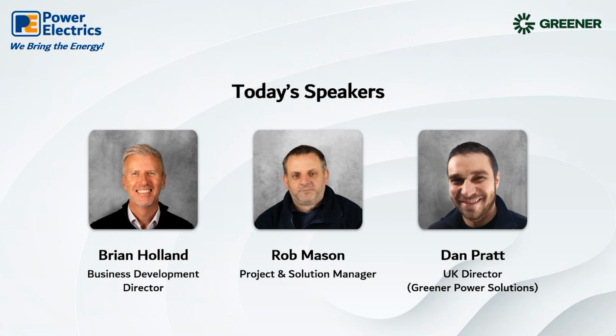Right, okay. And what capabilities do batteries have that customers or users wouldn't necessarily always realise? Well, I think peak power delivery is key. Temporary power solutions for applications where large dynamic loads are present make a very easy business case to utilise a large battery system. These are the sites where usually a large generator would be specified, but run very inefficiently due to the low load periods where machinery is not being used, or overnight after a shift finishes, or equally if the machinery in use has very high starting currents, but much lower running currents.